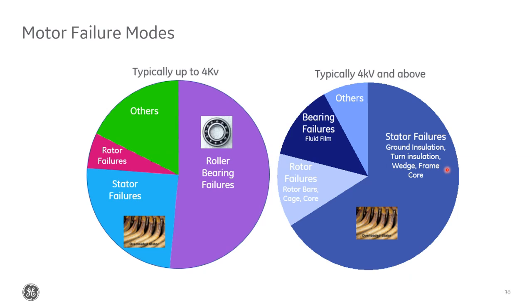A traditional motor protection relay like a 369 or 469 that uses a thermal model to estimate the temperature state of the motor really only provides stator protection. Unless you have RTDs, the only thing we're really considering is the amount of current flowing through the stator. So we can protect against things like overloads or short circuits. But you can see at both below and above 4 kV, we're still missing out on a lot of failures. Below 4 kV, our protection only really covers this blue part here for stator failures. We don't see over 50% of the typical failures that occur. We might catch these eventually, but by the time it gets bad enough that the RTDs would pick it up or a short happens, it would probably be way too late.